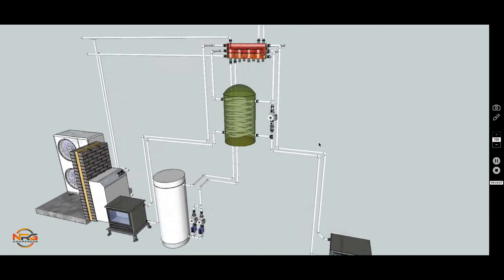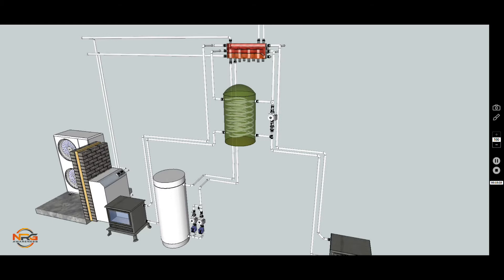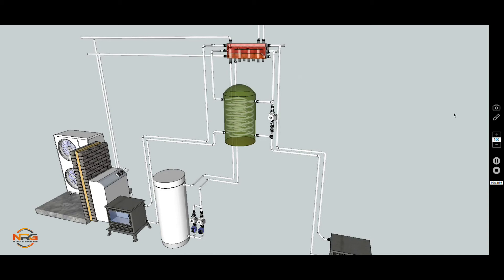If we want to put in a buffer that might be used to collect heat from the heat pump or to collect extraordinary heat that might be made available by the stoves, where zones have come up to temperature but there's no heat needed, that heat could be collected by a control system causing one of those pumps to operate down here. Those pumps have two functions: there's a pump and a valve, pump and a valve. This pump is facing out of the unit and will pull cold water from the end of the buffer out, and so pull hot water down through the first zone pipe and fill the buffer. And this pump is facing downwards and will pull cold water down from the lower chamber and push hot water that's stored in the buffer out. So you can see we have two options. We can either heat the buffer or we can cause the buffer to deliver its heat.